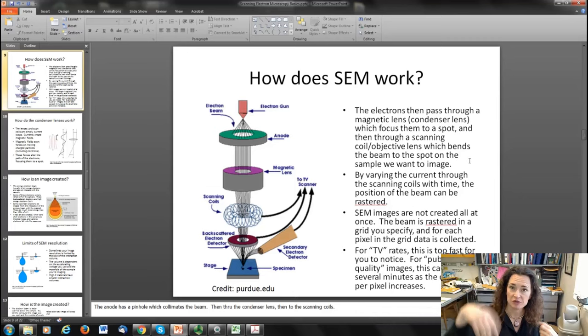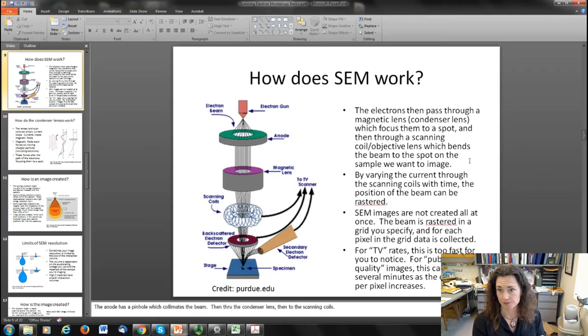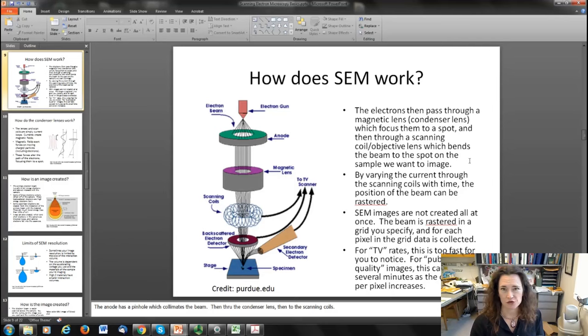Once the electrons are up to speed, they pass through a series of magnetic lenses. How many lenses depends on basically how expensive your SEM is, and that ultimately determines your final spot size and the resolution of the SEM. The magnetic lenses are often called condenser lenses because they condense the beam down, making it smaller to form it into a spot.